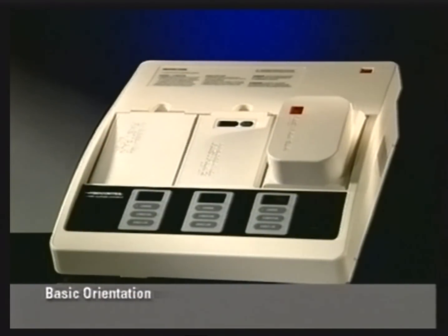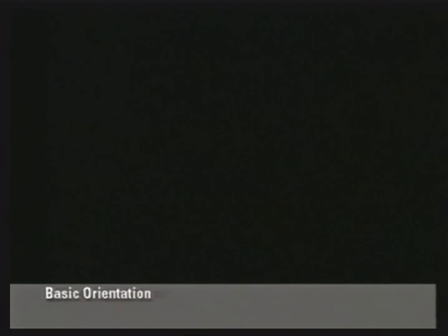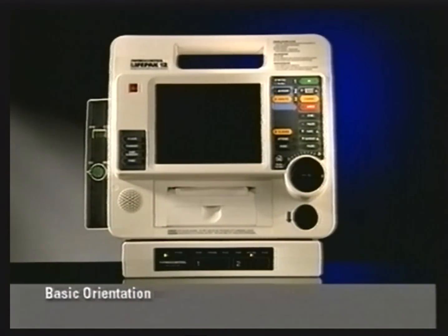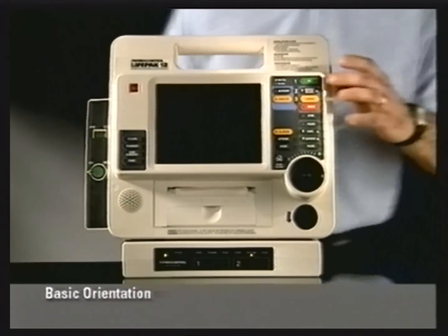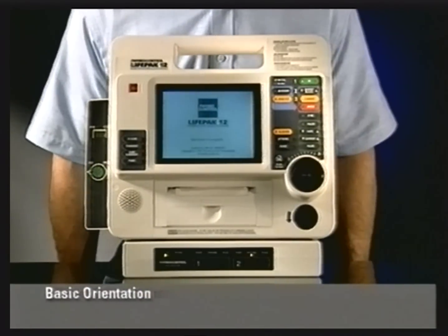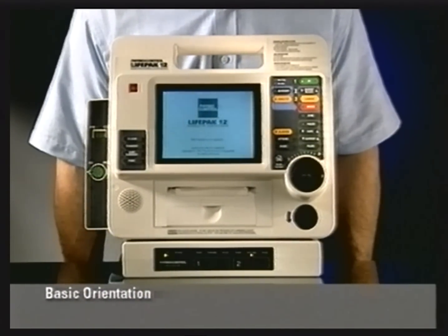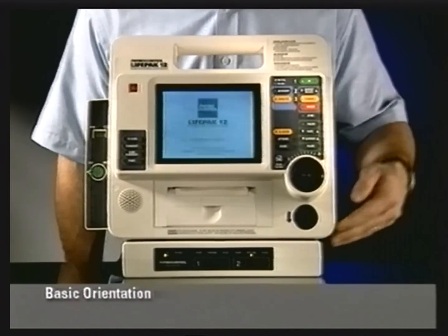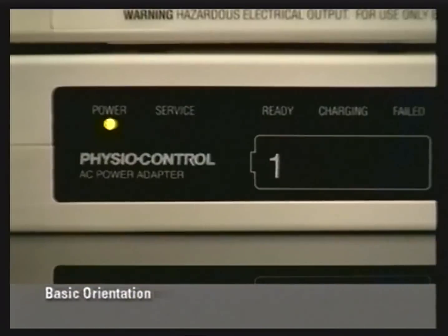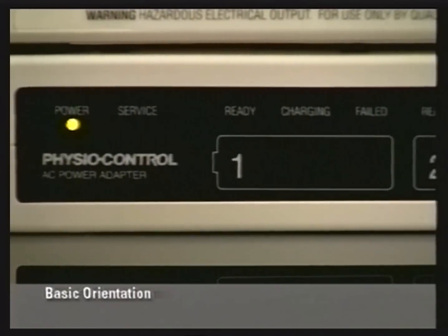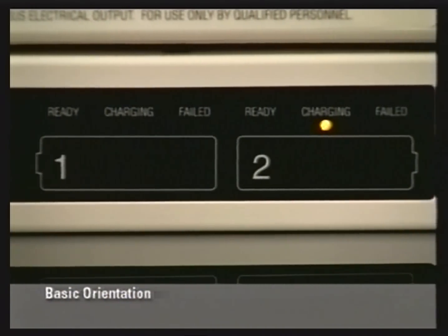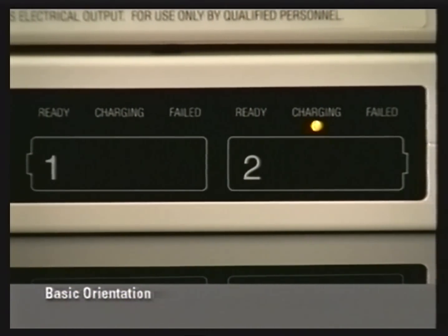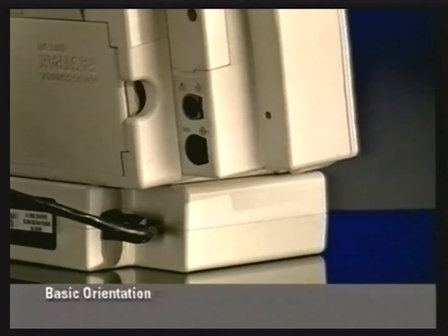The batteries require proper maintenance to optimize their performance. To charge and condition these batteries, use the Battery Support System 2. The AC and DC power adapters provide operating power to the Lifepak 12 defibrillator monitor and charge the installed batteries. The AC power adapter is shown here. The power adapters charge one battery at a time. Once the batteries are fully charged, they are trickle charged to maintain the charge level.